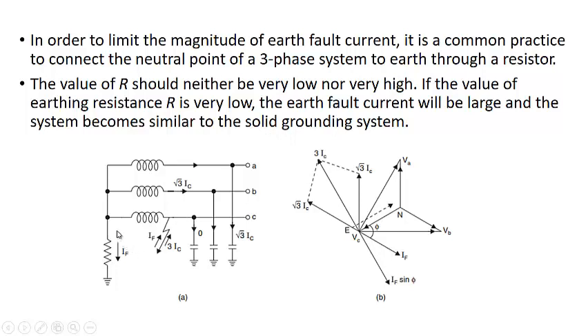Now you can see from here, when the fault occurs in case of C, the fault current will flow through this, and in the fault path we have an impedance of L and R. You can see that this is VA, this is VB, and this is IF. So IF will be lagging the neutral voltage, that is VCN, by an angle of phi depending upon the value of L and R. So IF will have a component IF sine phi, which may be directly in phase opposition to this fault current IC, and in this case a portion of this IC will nullify this fault current, and in this case arcing ground and over voltage will be eliminated.